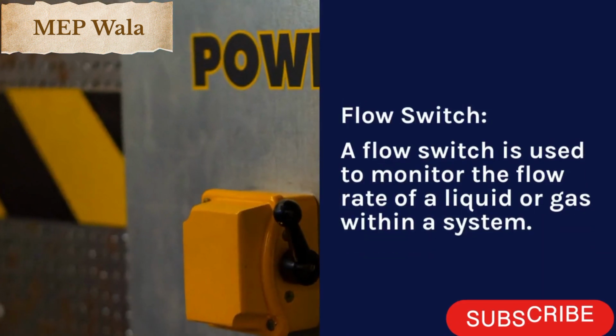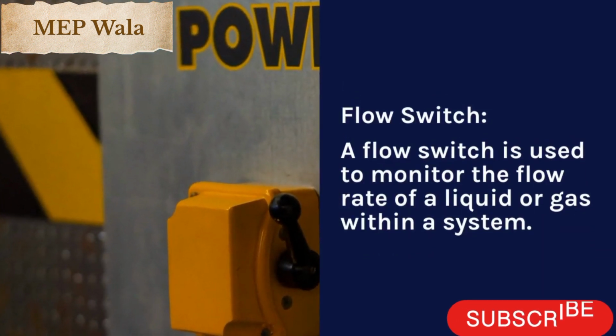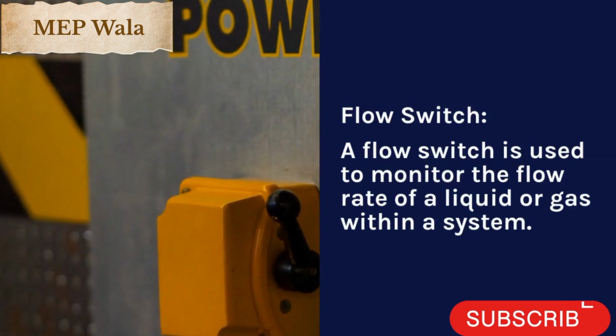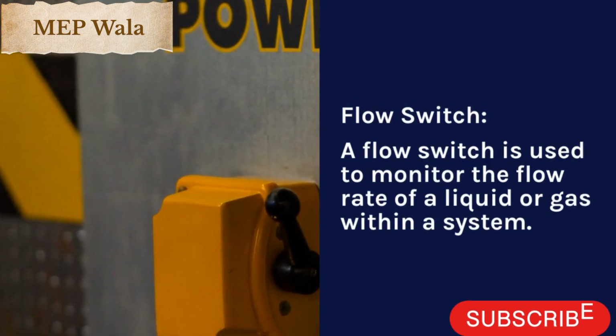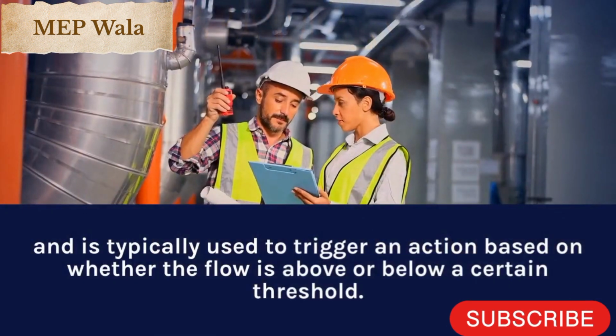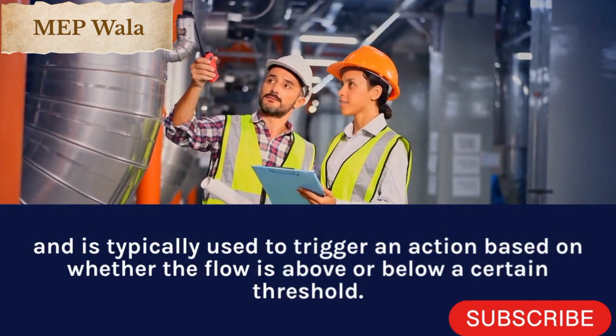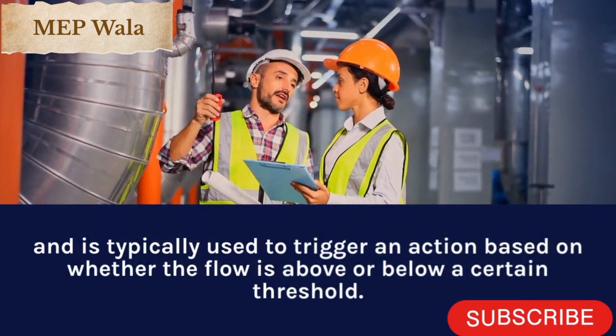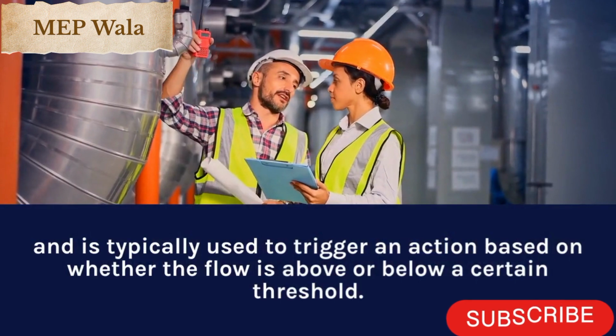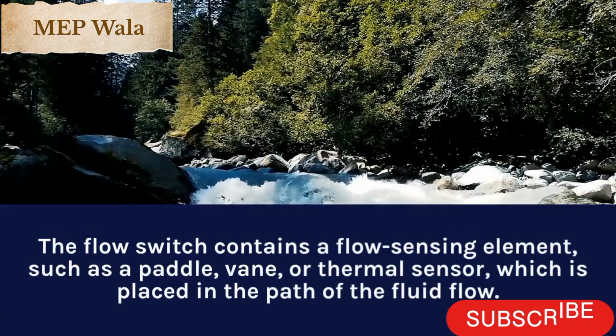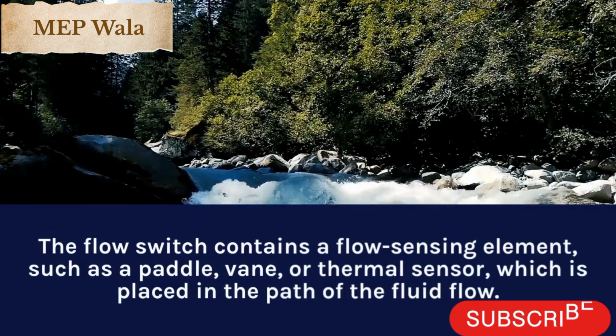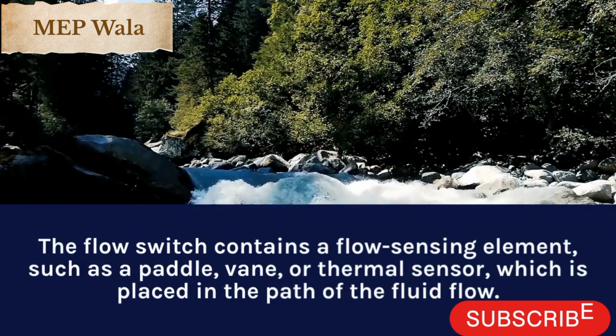Flow switch. A flow switch is used to monitor the flow rate of a liquid or gas within a system, and is typically used to trigger an action based on whether the flow is above or below a certain threshold. The flow switch contains a flow sensing element, such as a paddle, vane, or thermal sensor, which is placed in the path of the fluid flow.